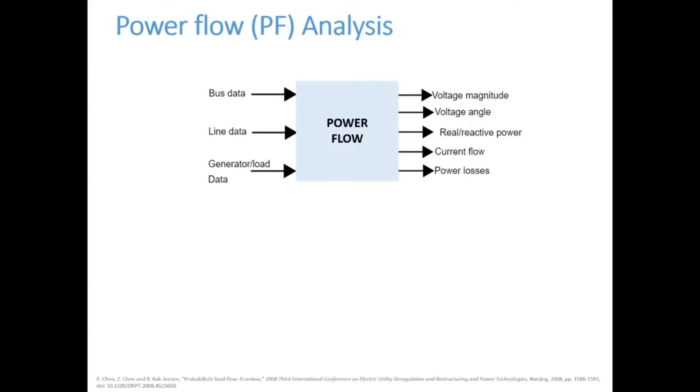It determines the steady state operating characteristics of the power system for a given load and generation. The primary outputs are the magnitude and phase angle of the voltage at each bus and the real and reactive power flows in each line. If these outputs are within the acceptable levels, it means that the power system is behaving normally.